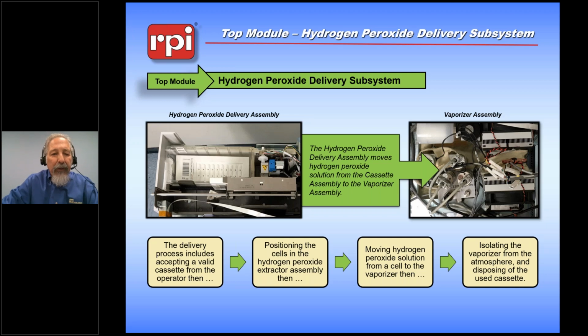Okay, so we're going to break those sections down. This is the hydrogen peroxide delivery system. And basically what you have is a cartridge. There are 10 openings in the cartridge. Each run requires 2 of these slots to make up the complete hydrogen peroxide delivery. In the process of putting in a cassette, there is a barcode reader that reads the barcode on the cassette. That barcode contains the out date for the cassette and information about that specific manufacturing process for that cassette.